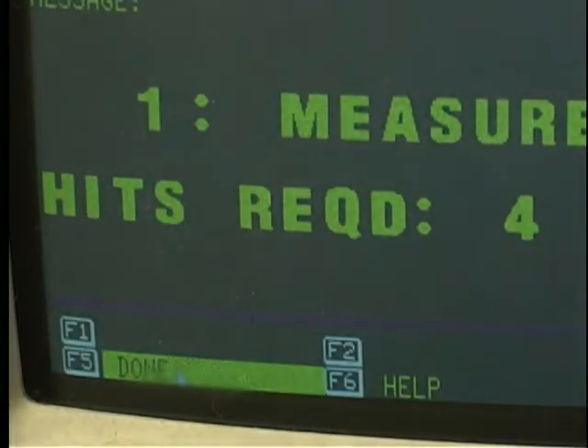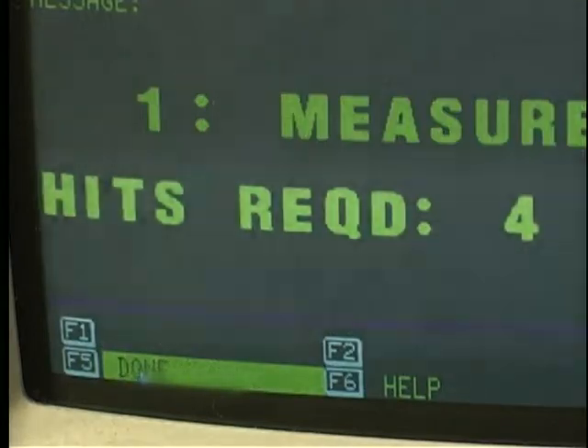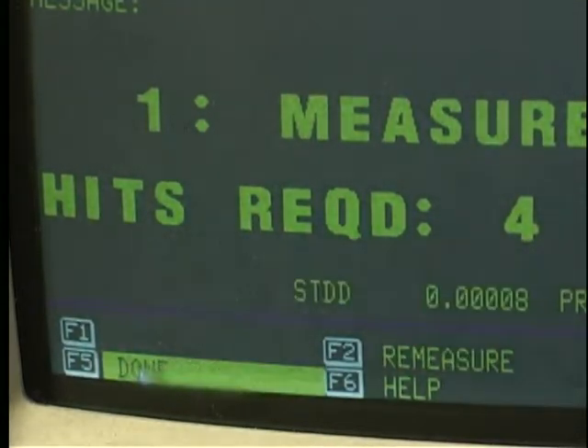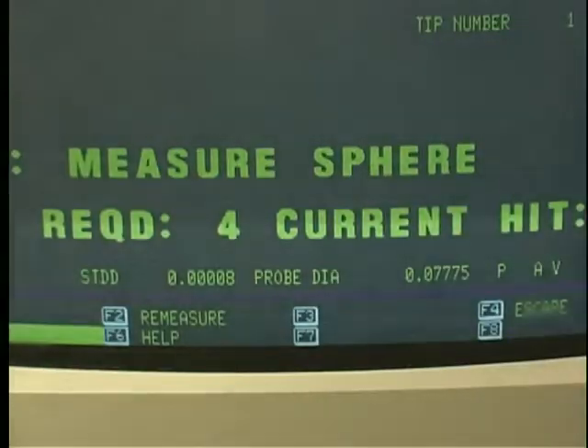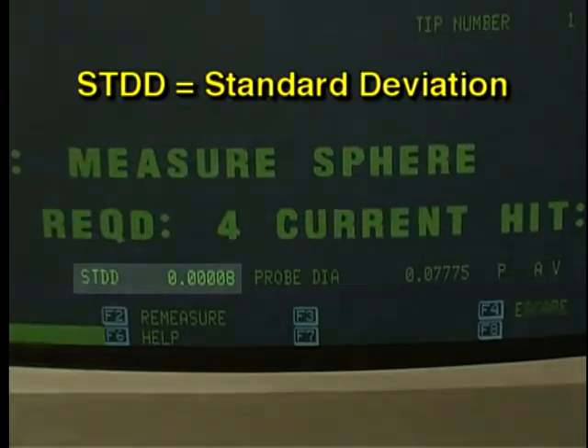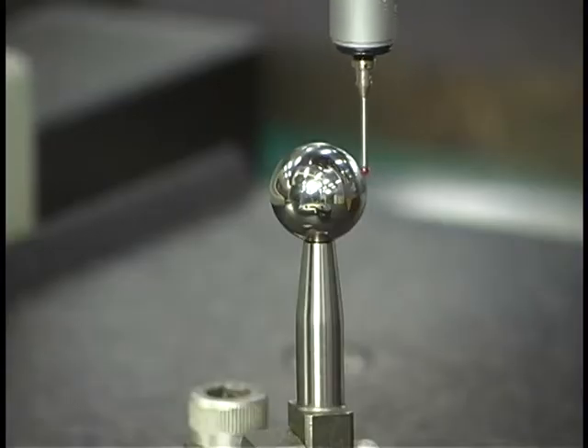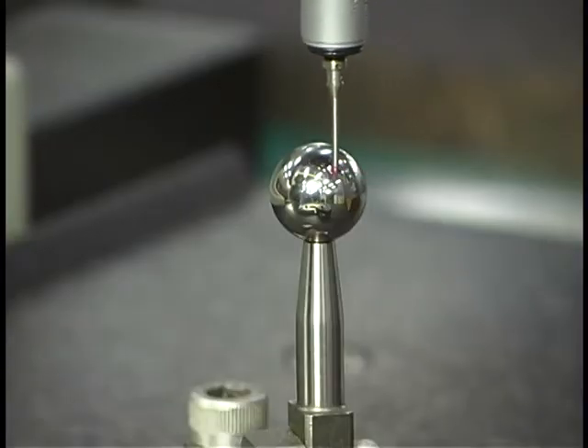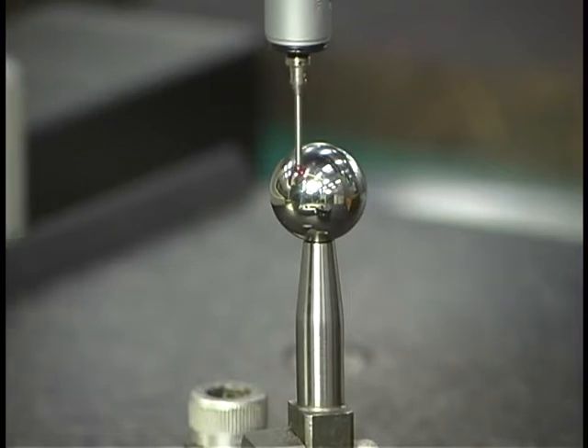The ninth and last hit is at the top of the sphere. After the last hit, the Done selection on the screen is highlighted. Clicking Done causes the computer to calculate the probe tip diameter. The display will show the calculated dimensions of the probe tip as well as the standard deviation for the measurements taken.